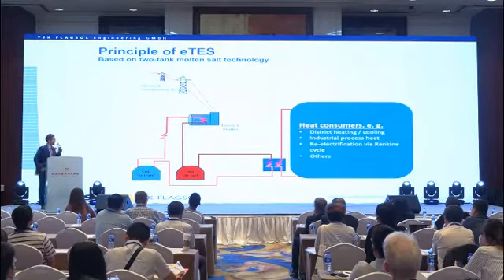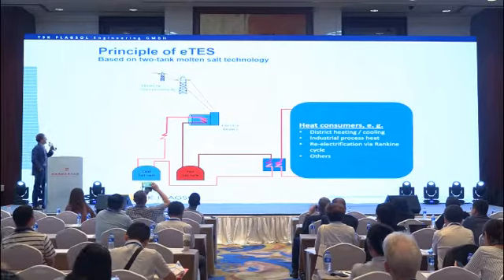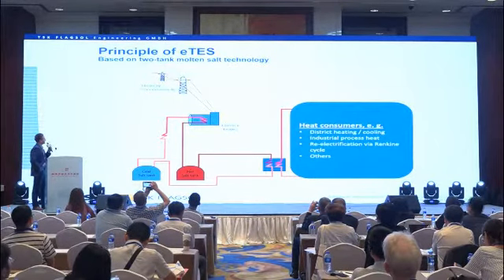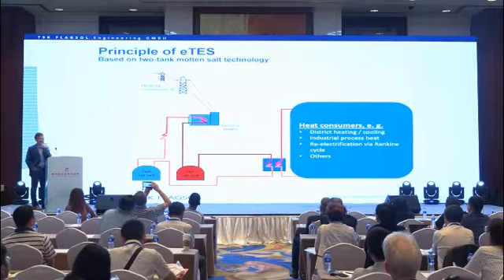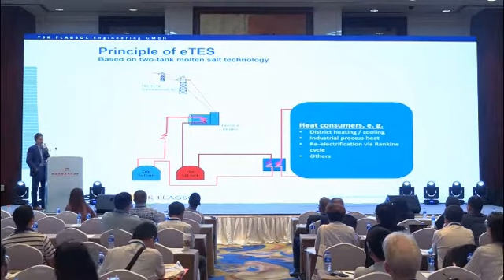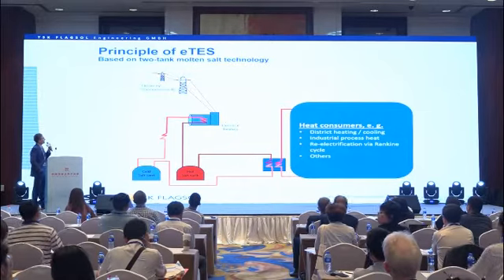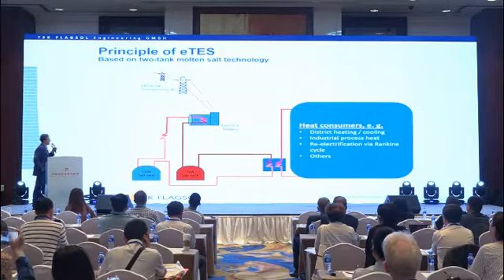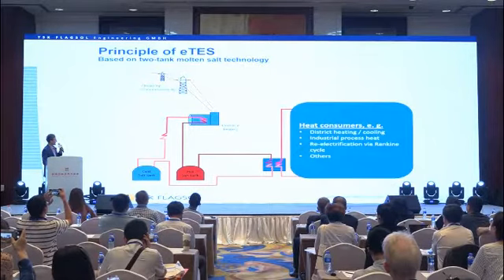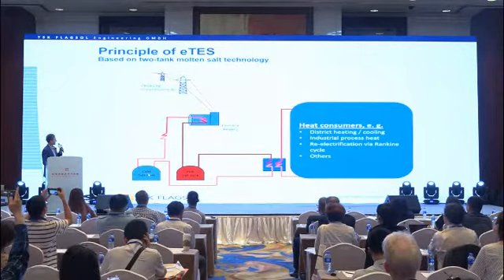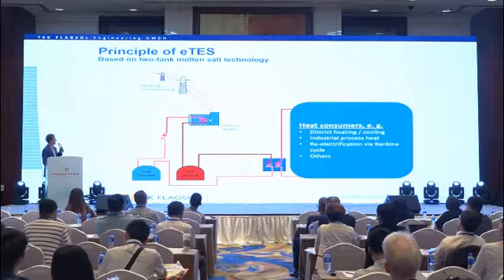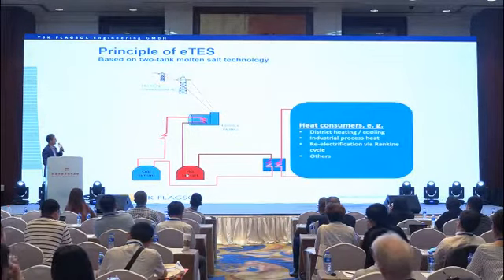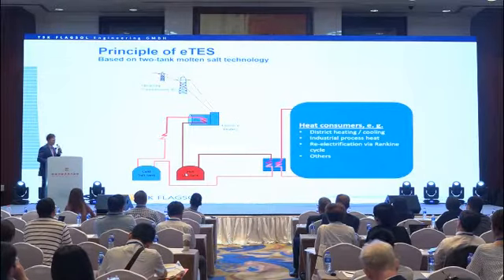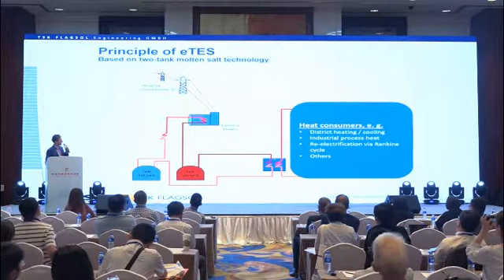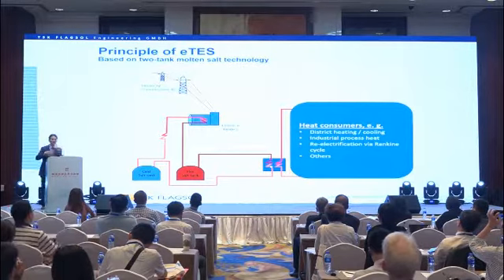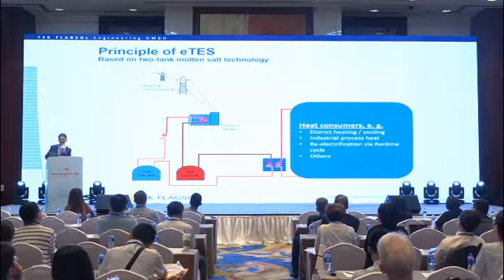So here you see the basic concept. In case we have excessive renewable energy in the grid, instead of curtailing this potential, we take it into the electrical heater and use molten salt coming from the cold tank, heating it in the electrical heater and storing it. Then, when there is demand, we bring this heat to another heat exchanger and provide it to any kind of heat consumer.